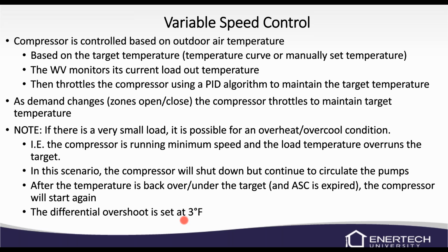If you have a small load zone and you're not using a buffer tank or a hydraulic separator, it's possible to overheat or overcool because the compressor is running as slow as it can and it's trying to maintain its temperature difference. If that happens, the compressor will shut down, but the pumps are going to continue to circulate through that zone or the zones that are calling. Once the temperature is back either under or over the target and the 3-minute short cycle has expired, then the compressor will go ahead and start again.